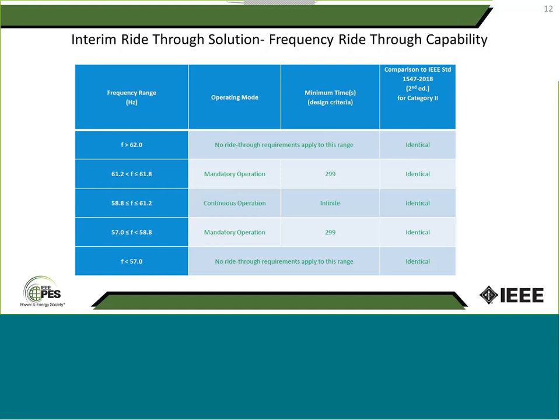And in the standard, how high does the standard 1547 go for voltage? So the standard, we really did not put any sort of voltage classification in it. We also removed that 10 MVA cap. We're just saying the standard applies to the distribution system interconnection. The reason that we couldn't do voltage classifications is that some utilities consider even 115 kV as their distribution wire. They may have some directly connected load, and for us, National Grid, our maximum distribution voltage is 13.8, and then we go to 23 kV and 69 kV for subtransmission. So we were not able to come to an agreement on the voltage class. We just left it open, but we specifically mentioned that this standard is only applicable to distribution systems, and then it will be at the utility's discretion to say what that distribution voltage is.